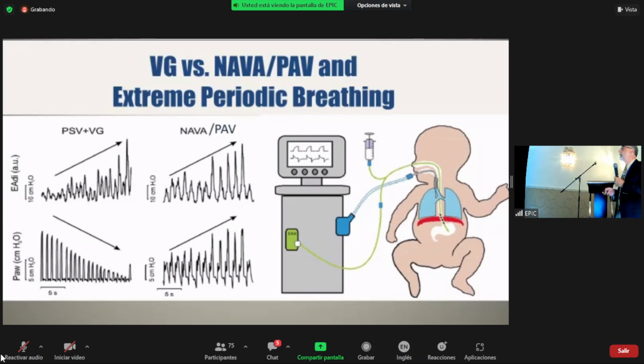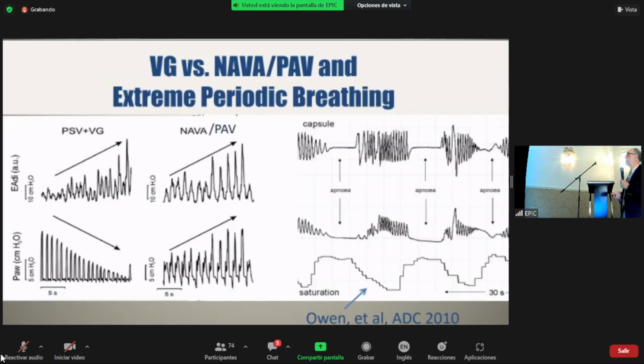In contrast, with volume targeted ventilation, if the baby hypoventilates or is apneic, the ventilator generates more pressure to try to maintain a stable tidal volume. And when the baby is generating very strong inspiratory effort, the pressure comes down to avoid excessively large tidal volume. The problem with NAVA is that babies with immature respiratory control tend to breathe like this. And if you superimpose positive feedback on this, you're probably going to run into all kinds of trouble.